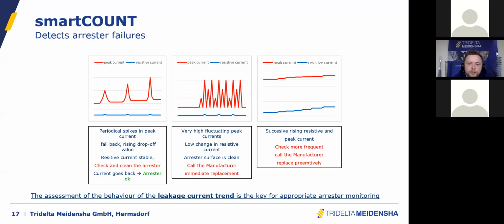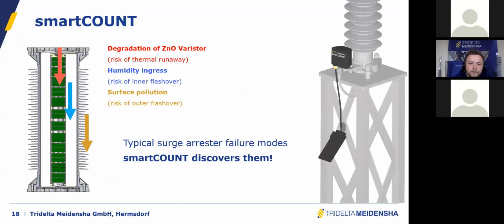If you don't have a leakage current trend, if you only have some single measurements of total current, or also some single measurements of total current and third harmonic current or resistive current, it will not give you the same information content like we get here from the smartCOUNT. So here, surge arrester monitoring and surge arrester health assessment takes place. Summarizing, the smartCOUNT is capable to discover all the typical failure modes which can appear in the surge arrester.